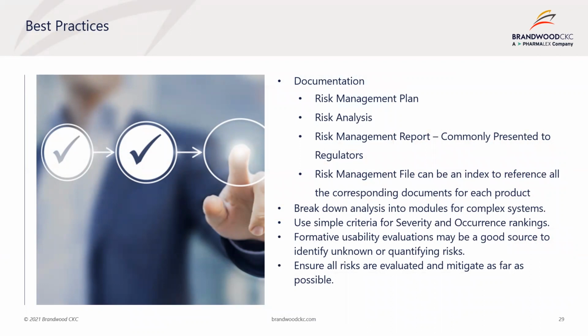Next, break down risk analysis into modules for complex systems. Also, use simple criteria for severity and occurrence rankings. Formative usability evaluations may be a good source to identify unknown or quantifying risks. It is important. You may not know risks exist until you allow the end user to use the product. Ensure all risks are evaluated and mitigated as far as possible.